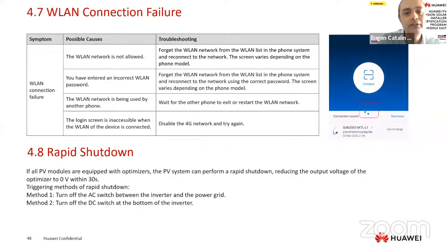The password I said incorrect password, or the Wi-Fi I said it is used by another phone. Yes, or the inverter is already busy with something. Anyway, if you cannot detect where and why the inverter is connected to another device or rejects you, the best way is to restart the inverter, and it will cut all the connections. It's fresh. You are sure that it's not connected anymore to any local device from the house.